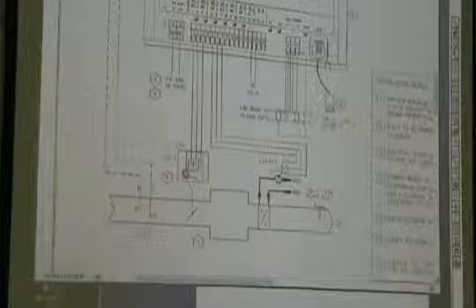So this setup is just the same TEC, the same everything. We just don't have a reheat coil. Now I can take this drawing right here and do constant volume hot water reheat. Everything here would be identical for constant volume hot water reheat. Okay, the only difference in the logic is that this airflow setpoint is just going to be the same all day long. It'll always be in the heat mode. We'll just be putting out a constant volume of air through here all day long, and our temperature control will be right here with the reheat.